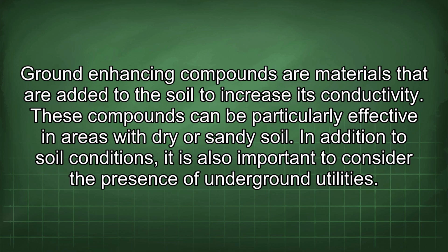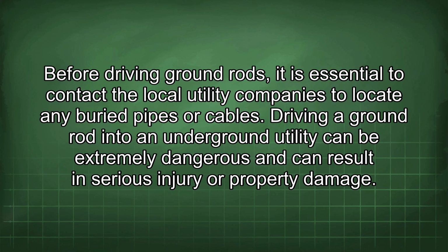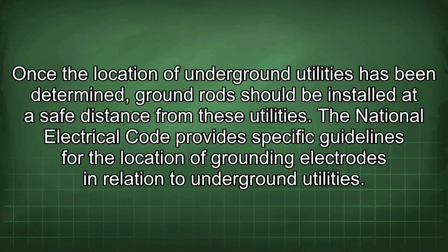In addition to soil conditions, it is also important to consider the presence of underground utilities. Before driving ground rods, it is essential to contact the local utility companies to locate any buried pipes or cables. Driving a ground rod into an underground utility can be extremely dangerous and can result in serious injury or property damage. Once the location of underground utilities has been determined, ground rods should be installed at a safe distance from these utilities. The National Electrical Code provides specific guidelines for the location of grounding electrodes in relation to underground utilities.